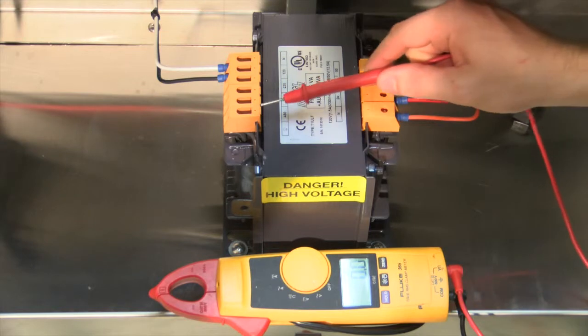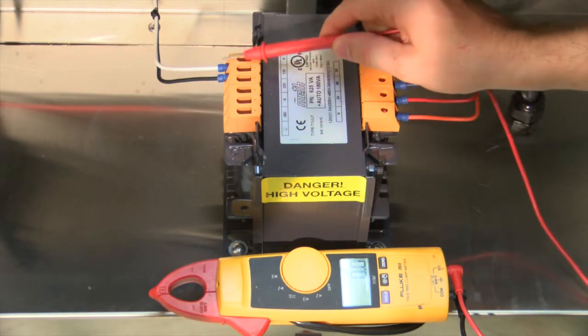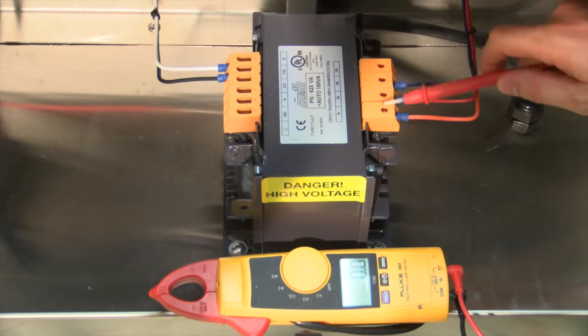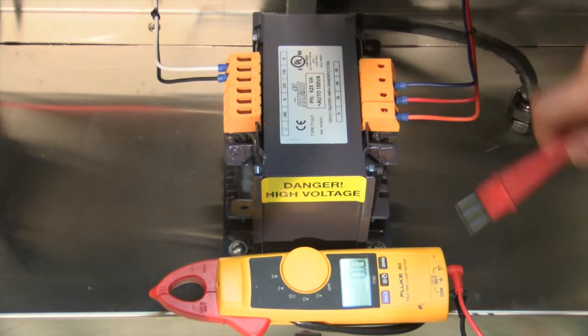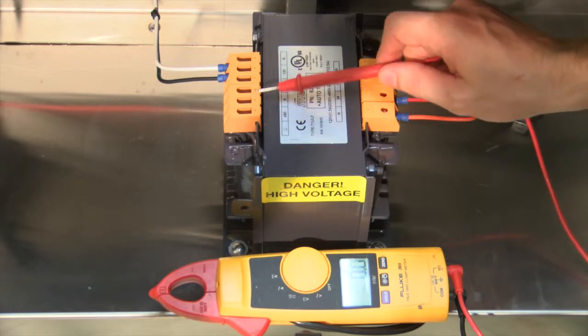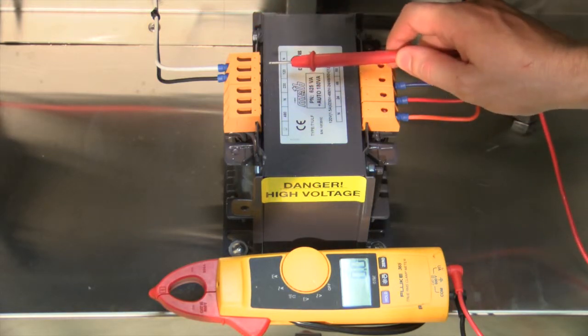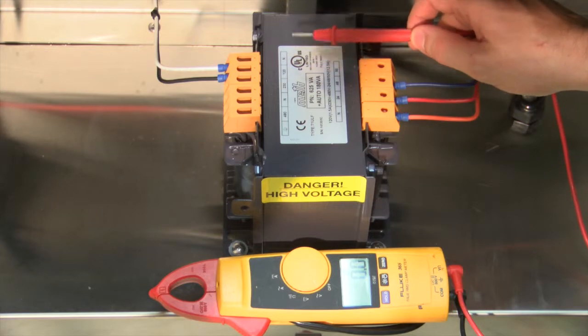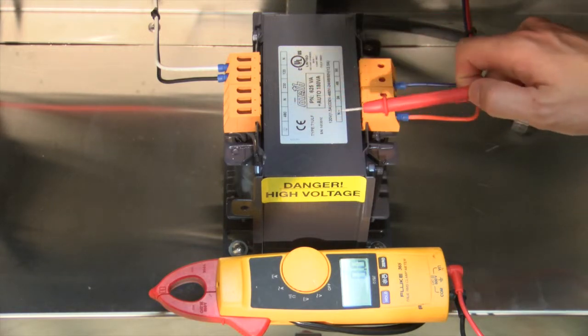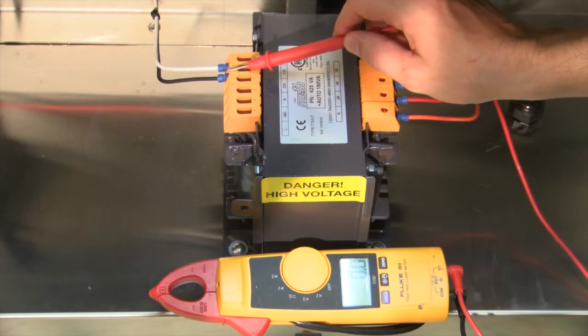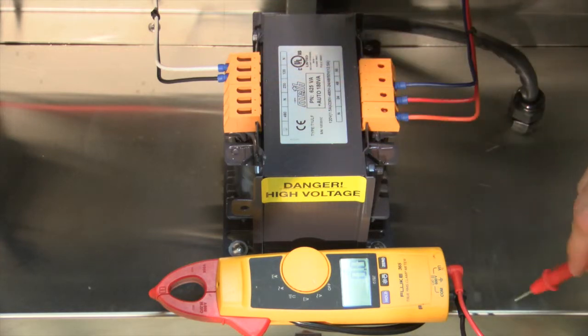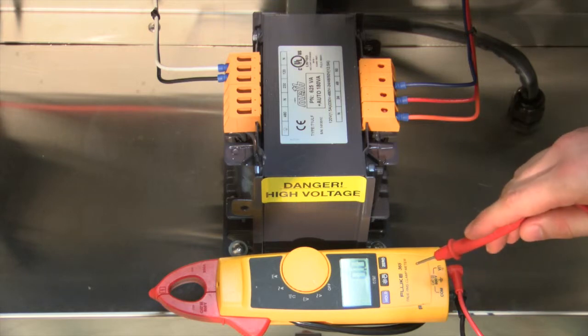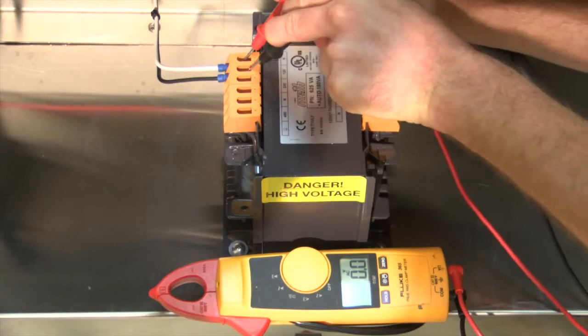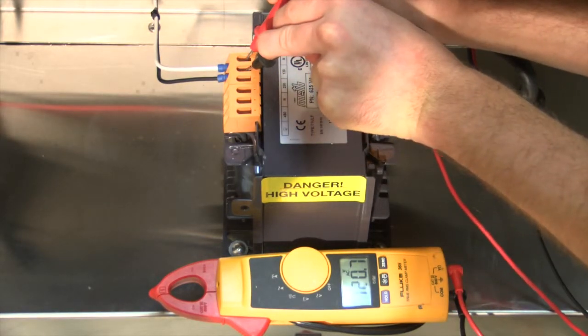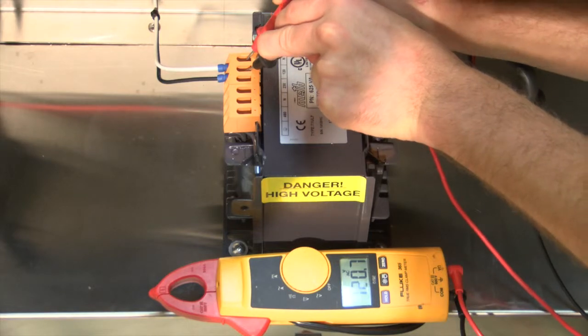On the transformer, you will see a primary side with a black and white wire, and a secondary side with an orange, red, and blue wire. The primary side of the transformer is the incoming power, in this case 120 VAC, although 230 and 480 are available. The black wire is the incoming 120, and the white wire is the neutral. You can verify this with a voltmeter or multimeter set on AC. Simply take your prongs to take a reading across the black and white, and you will see your 120 VAC.